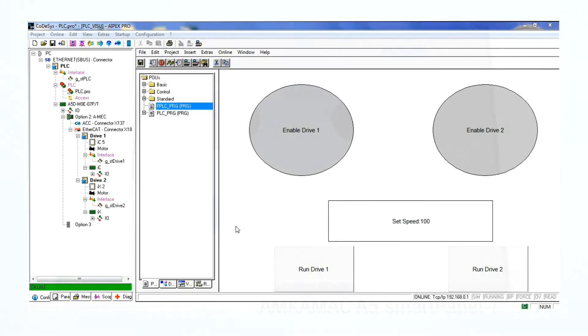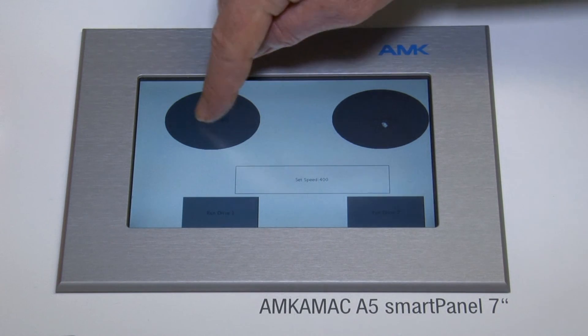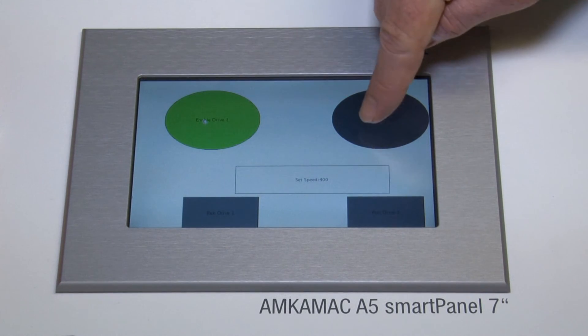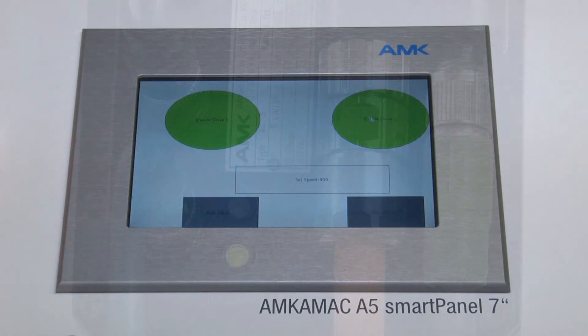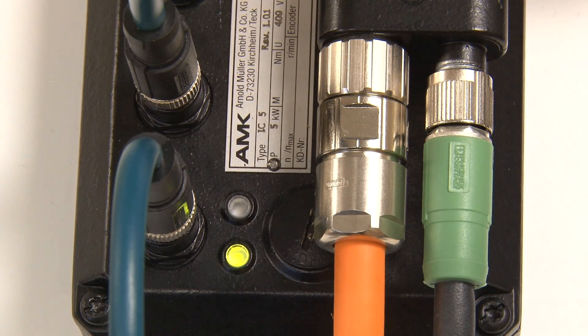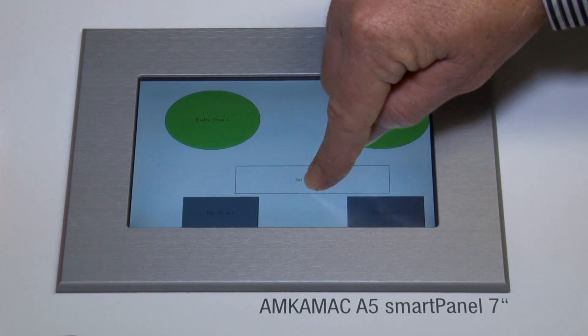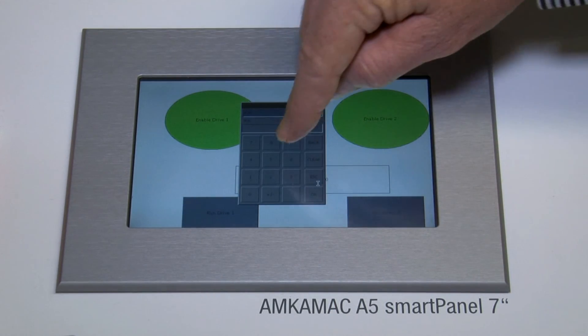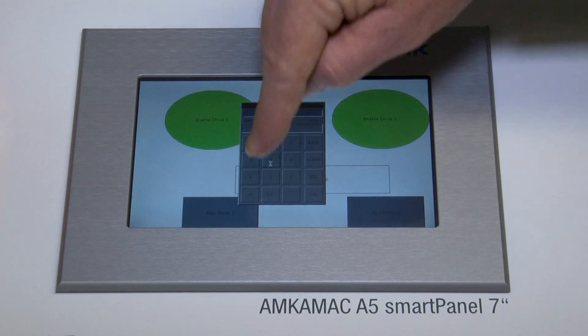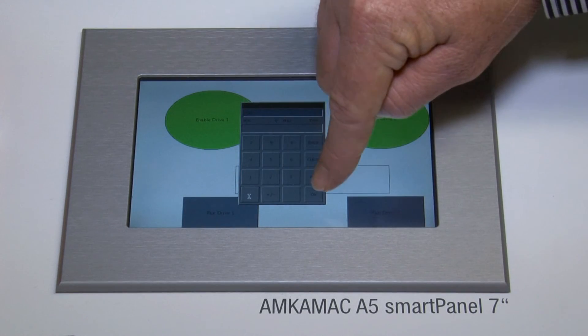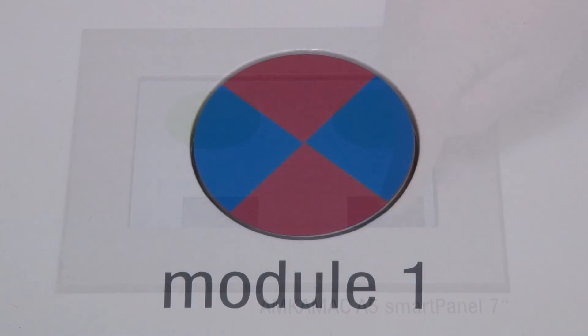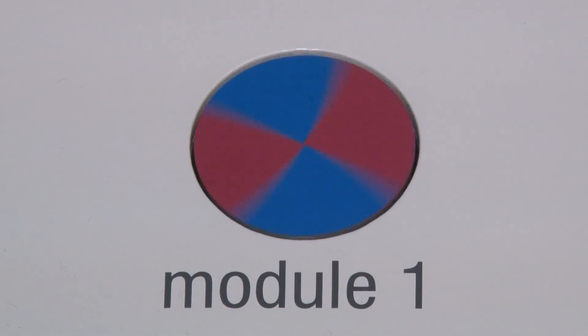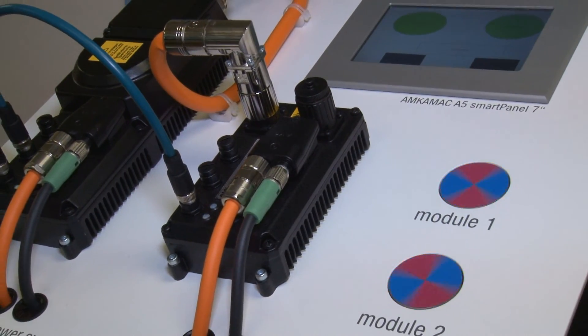Now we test our small program. Press the enable for both drives. The color should change when enabled. Also the LEDs on the units should change from steady state to blinking. Next press the set speed block and enter desired speed. Then press the run button for each drive. Both motors are now running in speed control with the value entered.